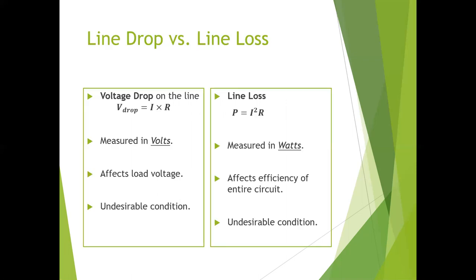To sum up line loss and line drop, here's a nice little chart for you. One is measured in volts, affects the load voltage and is undesirable. The other is measured in watts, affects the efficiency of the circuit and is also undesirable. Any questions regarding line loss or line drop?